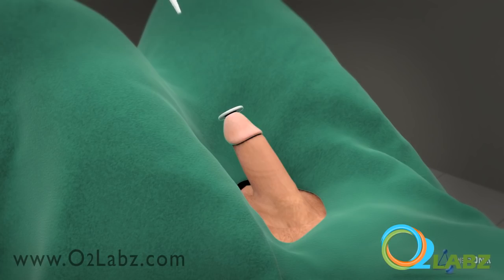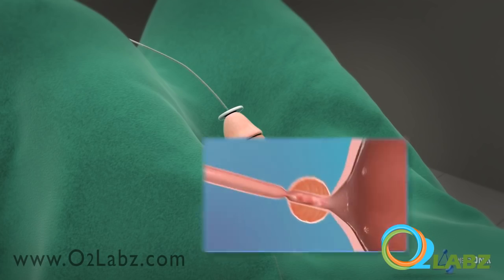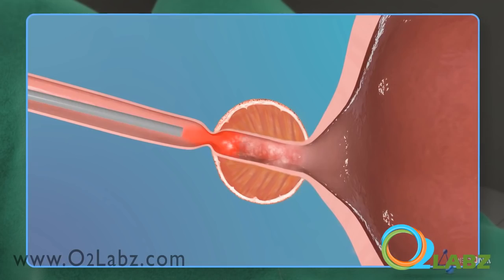At this point, the trigger is unlocked by pressing the safety lock. The trigger is squeezed several times to release the stent and deploy it in the correct position. The delivery tool is then retracted using gentle semicircular motions.